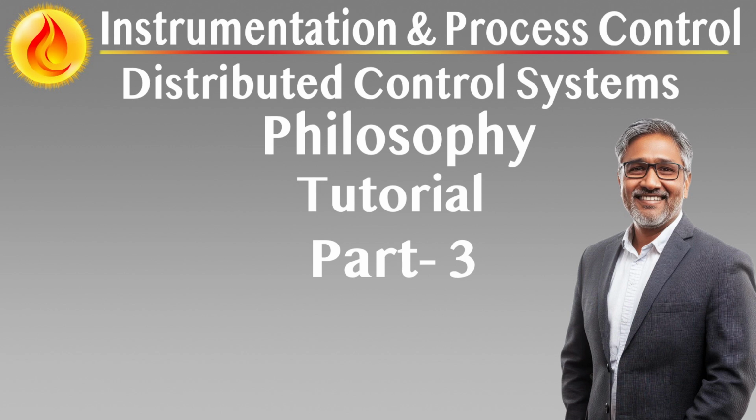Zoned actuation logic. Outputs are grouped and assigned to specific fire gas zones, allowing localized response, e.g. gas suppression in one module, deluge in another, without unnecessarily tripping unaffected systems. Dual-channel output verification. Outputs for critical systems include dual-channel confirmation. Both command signal and end-device feedback are required to validate actuation. Failure of either path raises a safety-critical maintenance alarm.